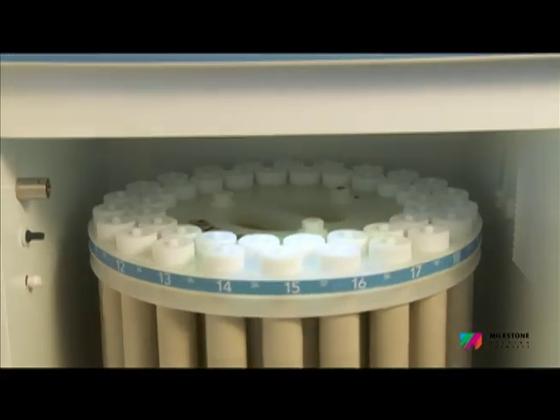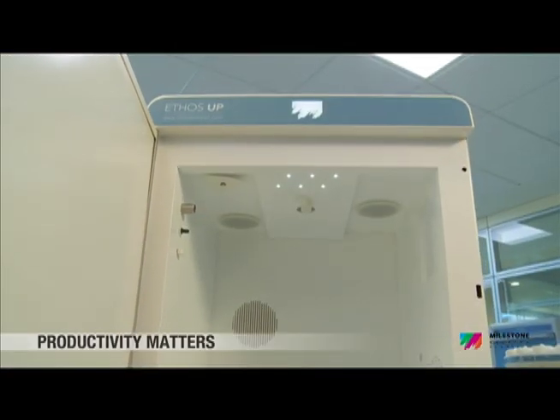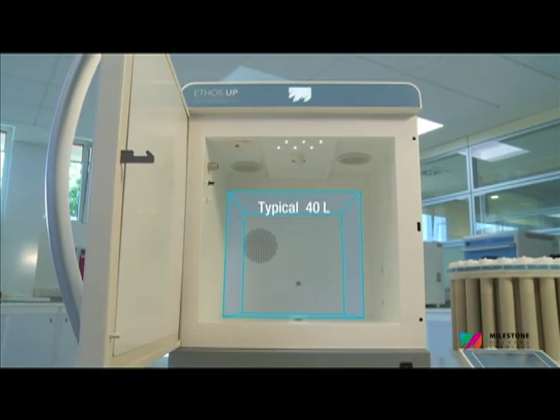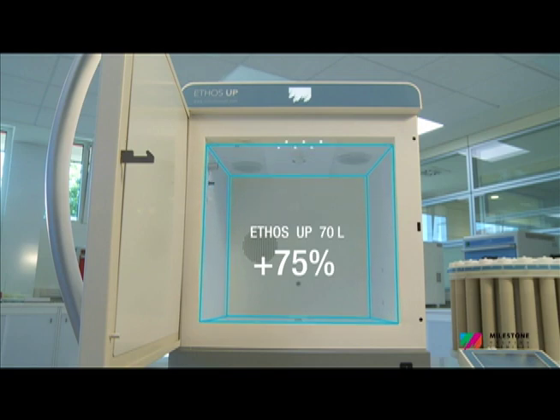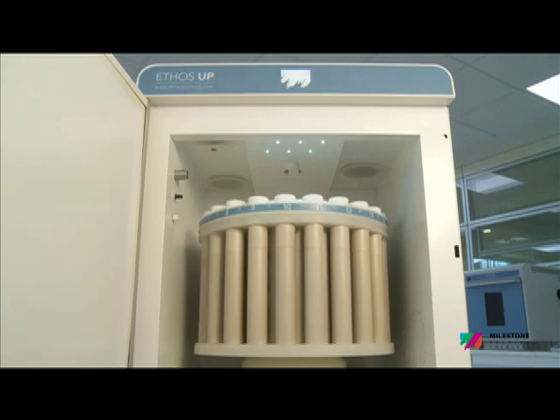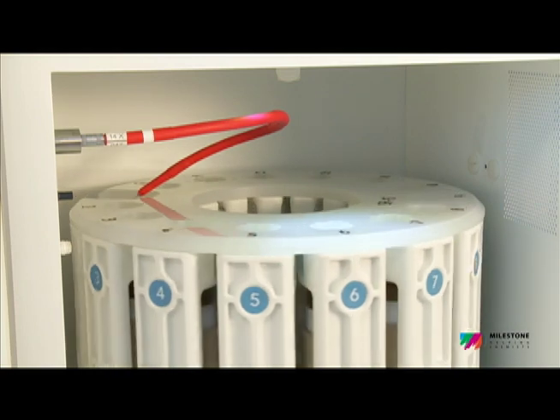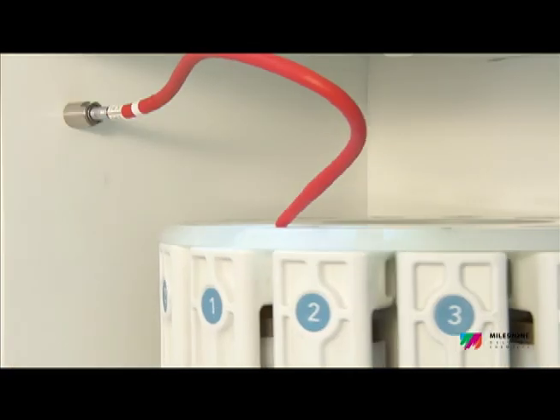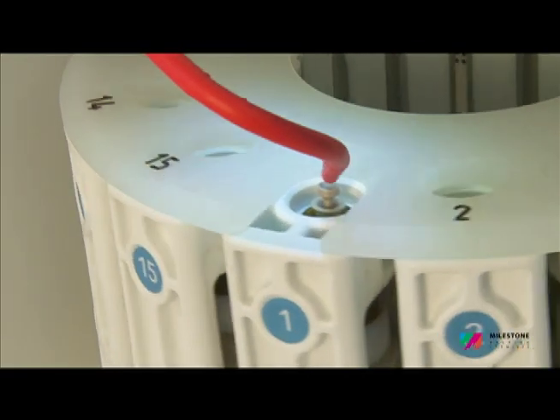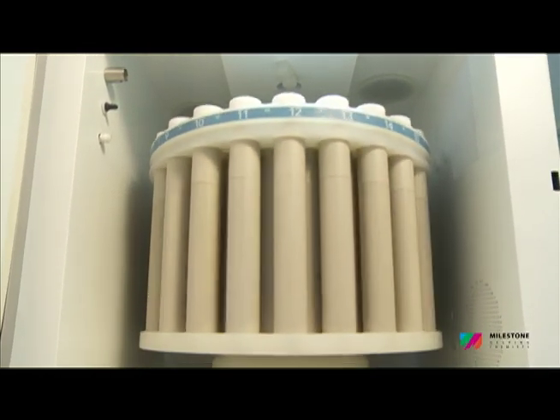The new Milestone Ethos Up microwave cavity has a volume in excess of 70 liters — by far the largest in the market. This has two important implications: first, bigger digestion rotors can be accommodated, improving sample preparation throughput; second, the microwave unit is inherently much safer because a larger cavity better contains gases escaping from vessels in case of sudden over-pressurization.